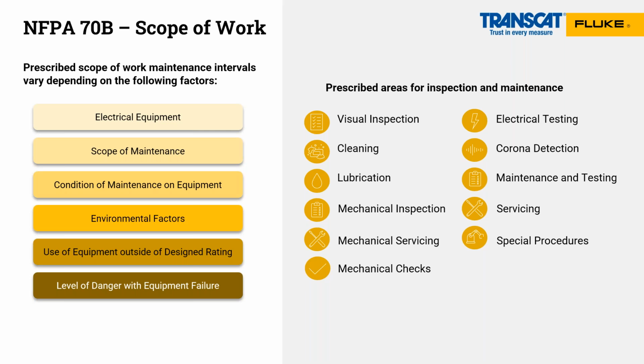So, kind of a busy slide. Scope of work is on the left. I'm going to look at my electrical equipment. I'm going to figure out my scope of maintenance. What am I going to do? I'm going to figure out the condition of the maintenance of the equipment. I'm going to look at any environmental factors. So obviously, things that are very hot, things that have dirt, grease and grime, things that can start to degrade power conductors and insulation. How is it being used outside the range it was designed for? I.e., am I running my motor hotter than it was designed for, which is going to be right on the nameplate? And what level of danger could be there if there was an absolute equipment failure happening here?